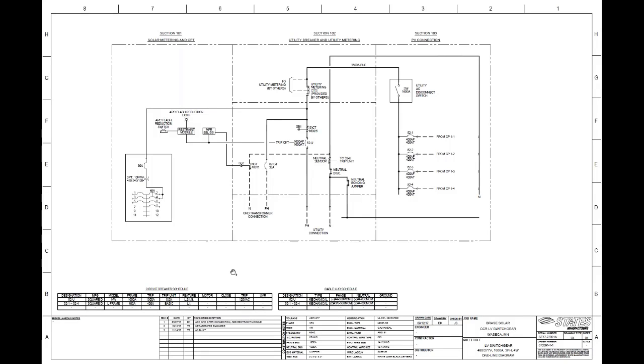When we do a switchboard, we'll actually do a takeoff. If you recall from the last drawing, the flow was left to right. Well, the beautiful thing was when they called us and told us we actually meant to go right to left, we were able to very easily, because of how States is set up, flip the 400 amp combiner breakers to the right side, have the AC utility AC disconnect switch in the right side of the cabinet, and we're right to left instead of left to right as the engineer's trying to show.